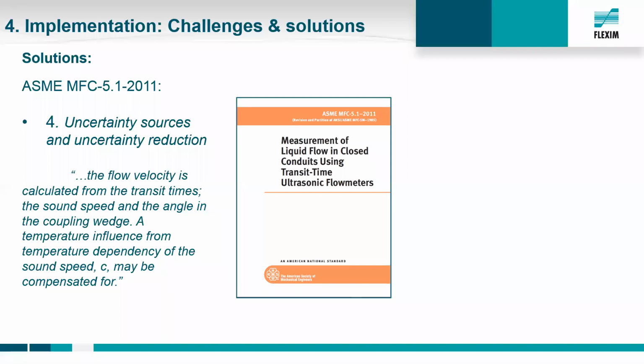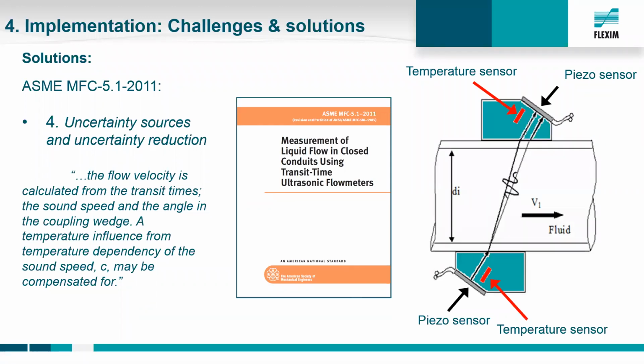And we found a solution for how to do it. It's a typical solution on other field instrumentation, but on ultrasonic clamp-on it's a rare approach, though we often face these challenges with temperature fluctuations in our applications, and from our experience, it is working. From laboratory tests in the PTB, we confirmed the function of this feature. We are integrating temperature probes, temperature sensors, into the transducer wedges themselves. The important approach is that we integrate the temperature sensors in each transducer wedge of one pair. One pair always consists of at least two transducer wedges, and it is important to have temperature sensors in each transducer head, in each transducer wedge.